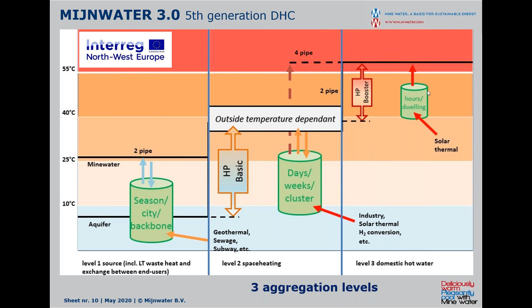From this point we have to raise the temperature, which we do weather-dependent mainly for space heating, using central heat pumps, and we try to build a buffer, maybe around 30 to 50 degrees Celsius, for a neighborhood or district where we use this energy. From there we go to the buildings, individual units and complexes. At the building level, we have a booster heat pump that finally brings it to the demanded temperature, like for domestic hot water, at least 60 degrees Celsius. There we can also have small vessels, boiler vessels, which store this high temperature energy. So it's a buildup of multiple levels and aggregation levels of sources and buffers, which we try to let work together and reinforce each other.